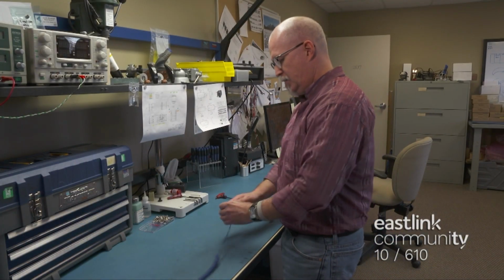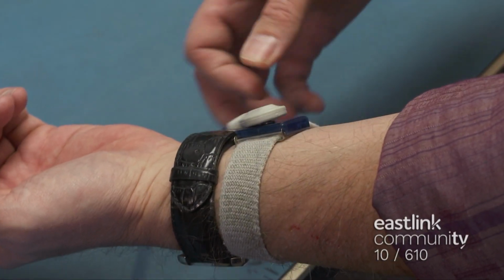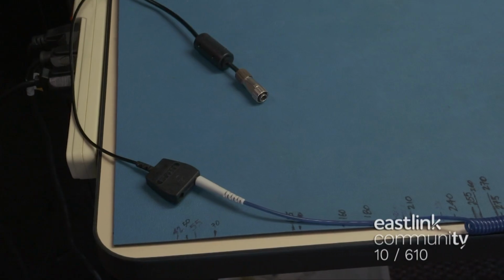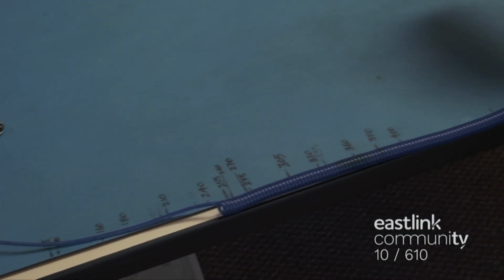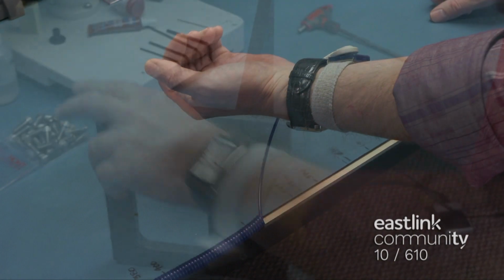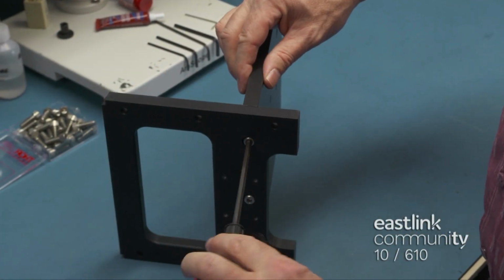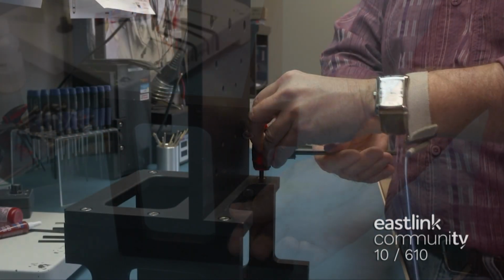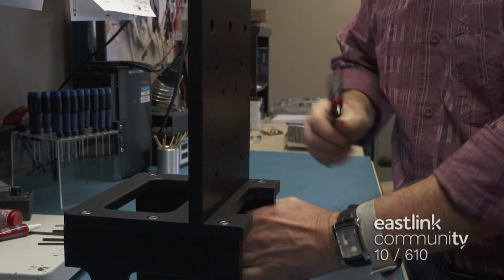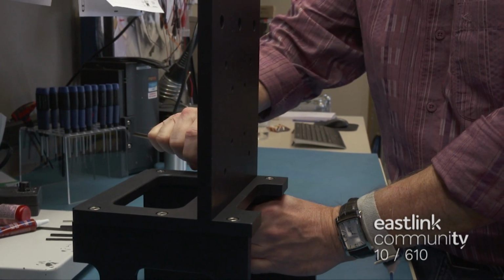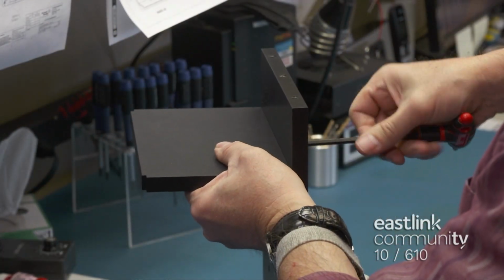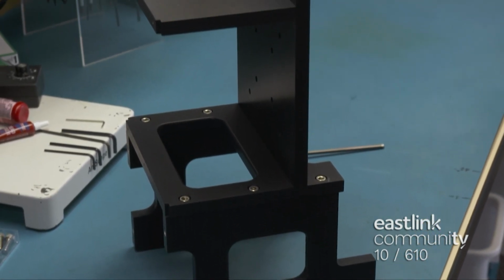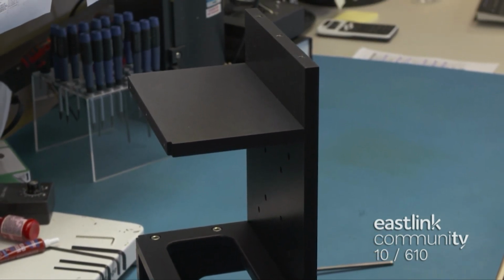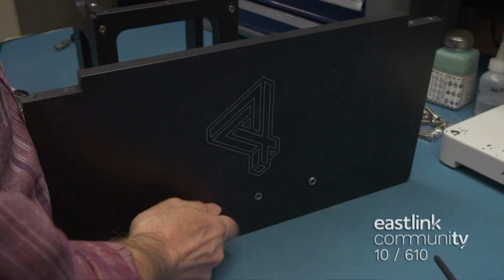To begin building the microscope, the technologist connects himself to a grounding strap. This eliminates the possibility of static electricity damaging the electronics in the unit. The technician assembles the frame using screws and a hex key. An additional tool is used to add some extra torque, ensuring the screws are nice and tight. Each piece of the frame is built up in the same way. The microscope frame is made from anodized plate aluminum, a material known for its rigidity and lightweight. Once the frame is complete, the front panel is secured.